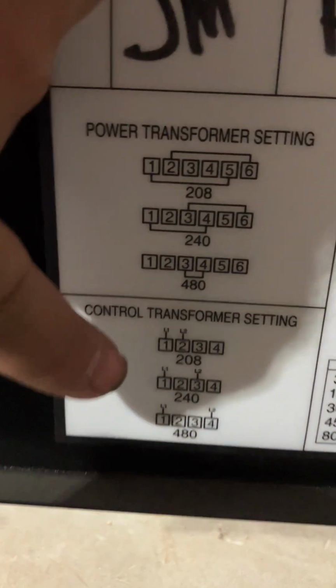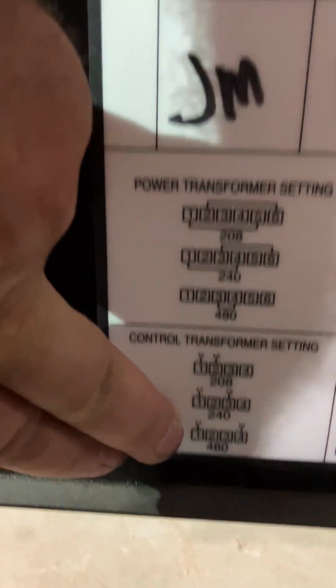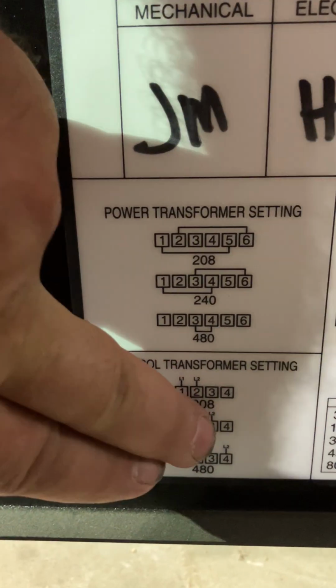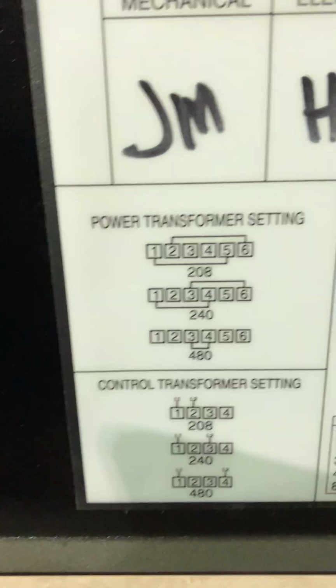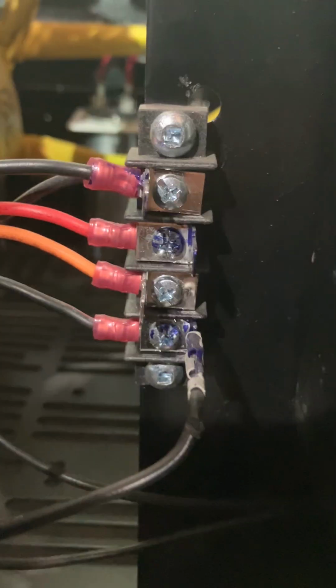And you can see there, I'm having trouble reading it now, but I think that says 1, 2, 3, 4. So we're going to leave 1. Notice 1 is common in all three voltages, but you tap a different 2, 3, or 4, depending on the voltage that you're putting to it. And again, we've already done it, but there it is. On the side it says 1, 2, 3, 4. We did leave 1 where it was, and then made sure the 4th was tapped, because we're feeding it 480 volts.